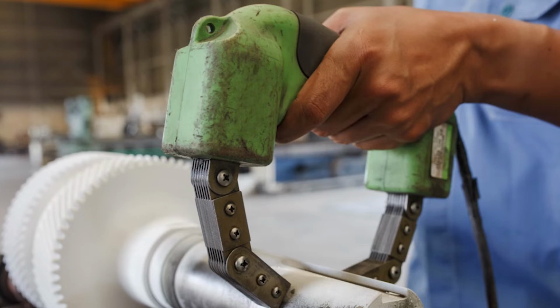We determined through that study that it was about 5 mil of thickness that you could actually still see parts going through a coating. But again, when you are dealing with mag particle and you're dealing with a coated surface, if something is seen, it should always be cleaned and verified. I would never feel comfortable certifying a part if it did have a coating and I saw something.